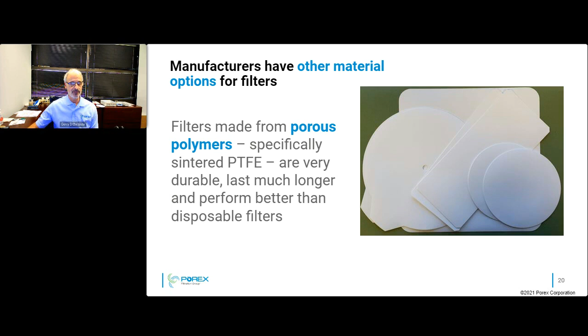And I hope you appreciate my little graphic on the right. That's the pile of disposable filters that are needed for a container versus the one reusable filter for the life. So disposable filters are soft, easy to form, fragile, prone to damage and contamination, whereas reusable filters are very robust, very strong. They don't rip or tear easily, can't really puncture them, and it really protects the container sterility while it's being used. Disposable filters are susceptible to incorrect installation, which can reduce labor efficiency and product efficacy, whereas the one reusable filter is used for thousands of cycles and has no reliance on service or accidental misuse because it's designed to be used multiple times.